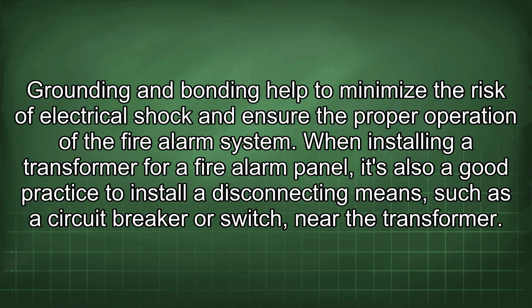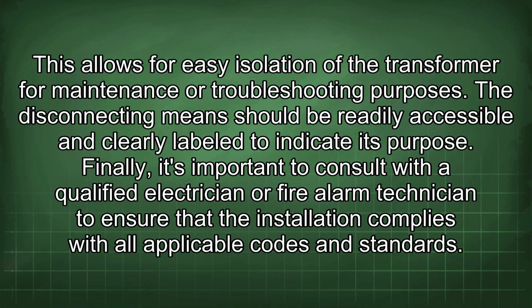When installing a transformer for a fire alarm panel, it's also a good practice to install a disconnecting means, such as a circuit breaker or switch, near the transformer. This allows for easy isolation of the transformer for maintenance or troubleshooting purposes. The disconnecting means should be readily accessible and clearly labeled to indicate its purpose.